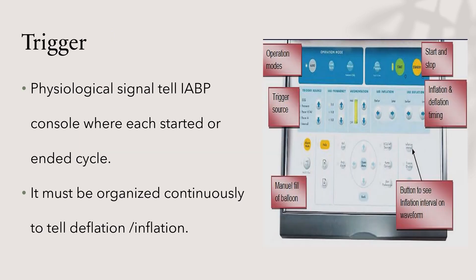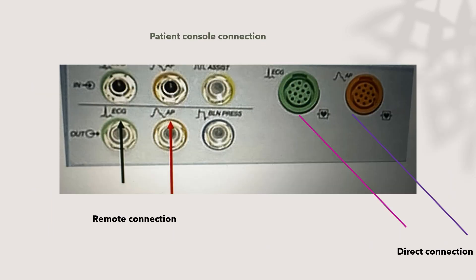The trigger is the physiological signal to the intra-aortic balloon console indicating when to start or end the cycle. It must operate continuously to control inflation and deflation of the balloon. Looking at the console, we can see the source of trigger and the patient console connection — how we connect to the trigger.